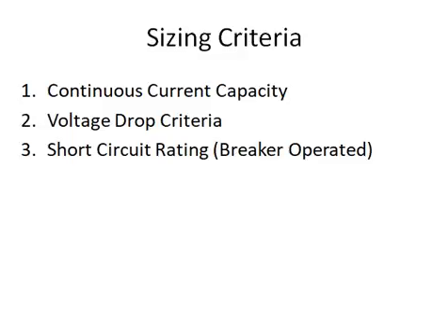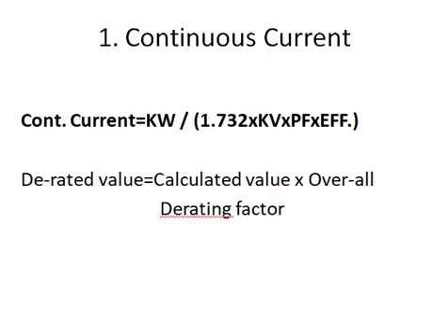There are three criteria for cable sizing calculation. Number one is continuous current capability. Number two is voltage drop criteria. And number three is short circuit current rating. The first two criteria are applicable for small rating motors, that means MCCB operated motor feeders. Number three — short circuit rating — is applicable only for breaker operated feeders. So all three criteria shall be fulfilled for breaker operated feeders.